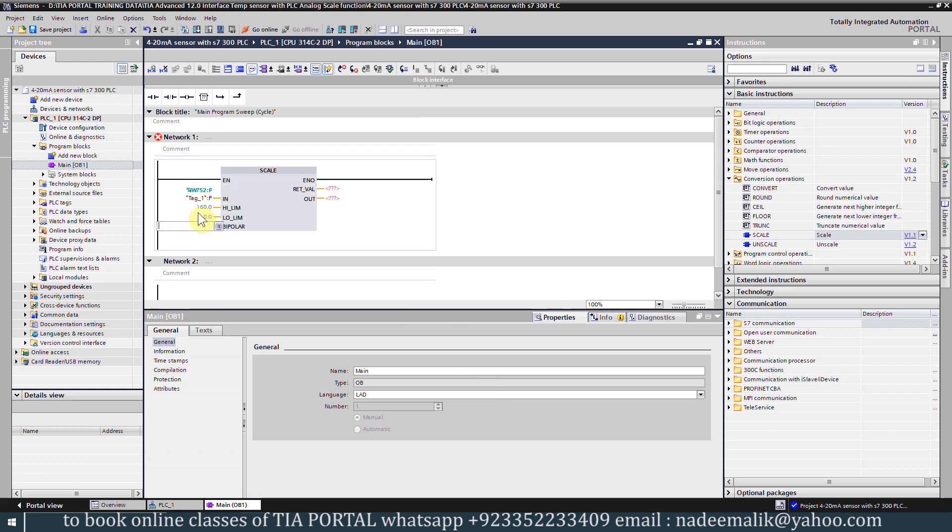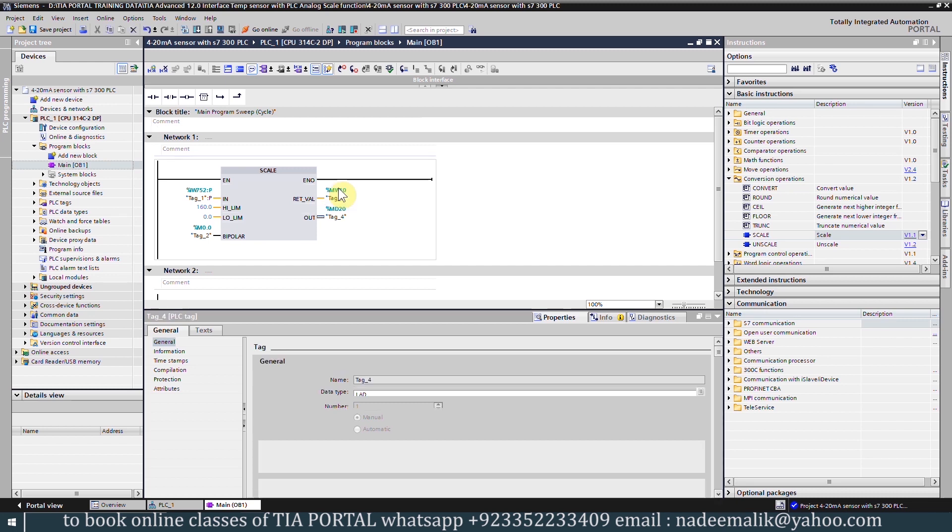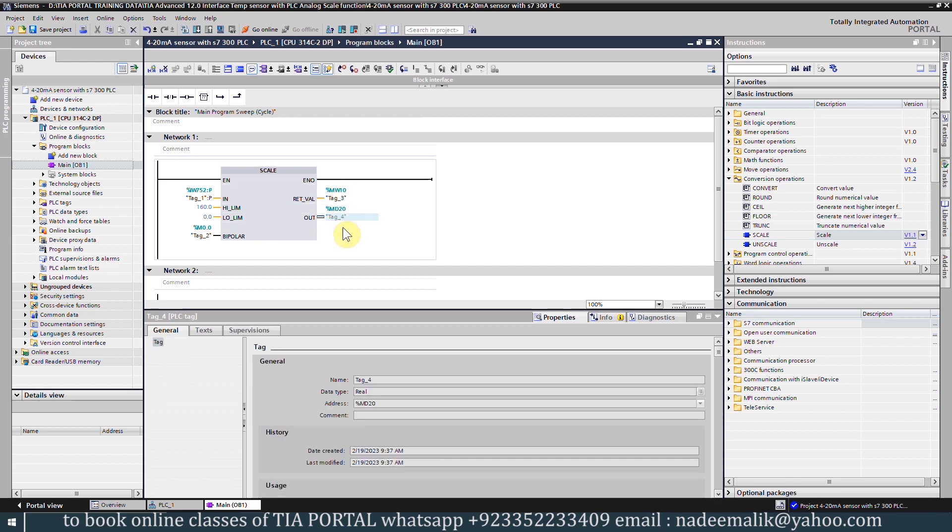In the bipolar input we can assign a memory bit M0.0. In the return value output we will enter memory word 10 to record any errors in the scale function. In the OUT we will enter MD10 which is the double data register to save the scaled temperature values.